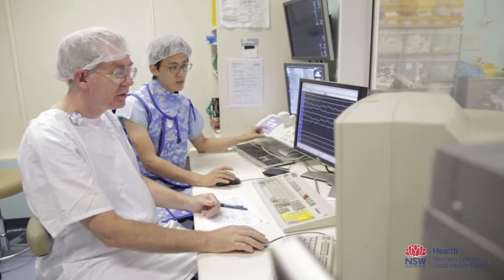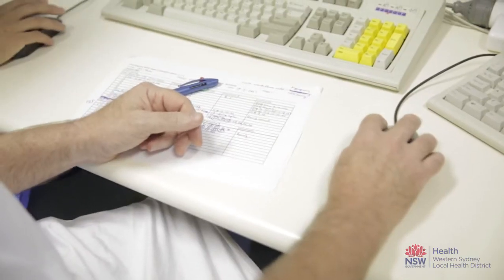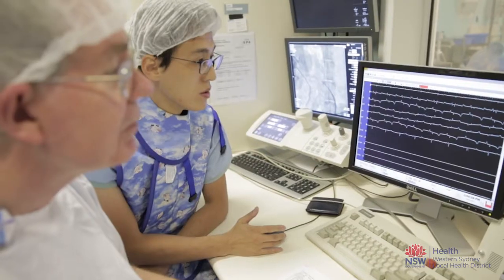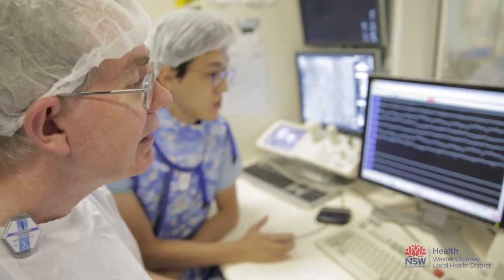The kidney nerves run around the kidney artery. Currently, renal denervation systems use radiofrequency ablation from the artery lumen to target these nerves. The problem with these denervation systems is that they have to burn through the renal artery first before getting to the nerves, and you can't burn all the way around the renal artery to get all of the nerves.